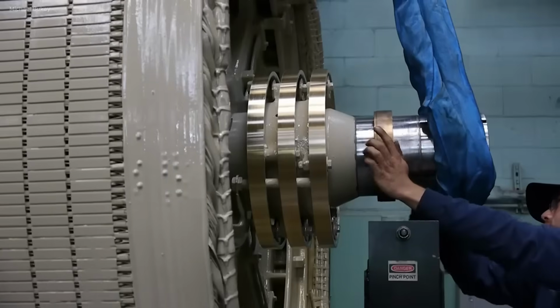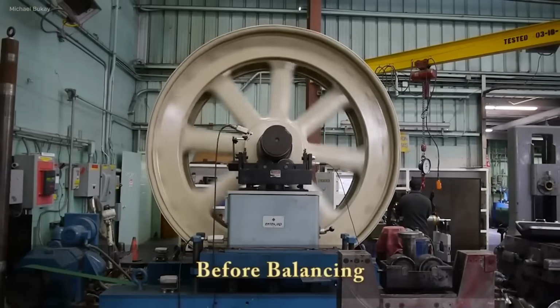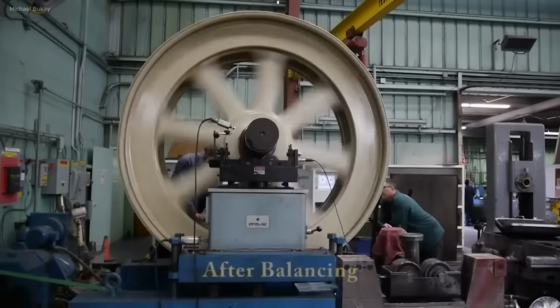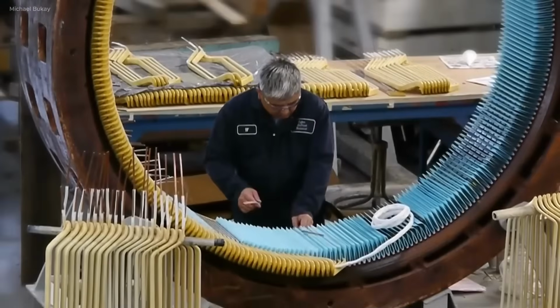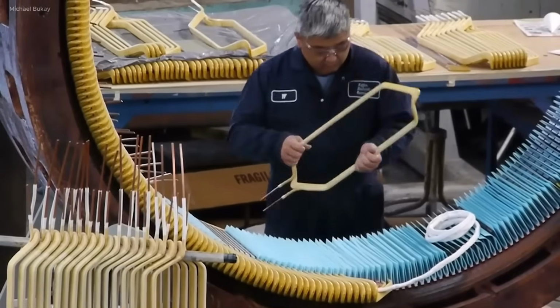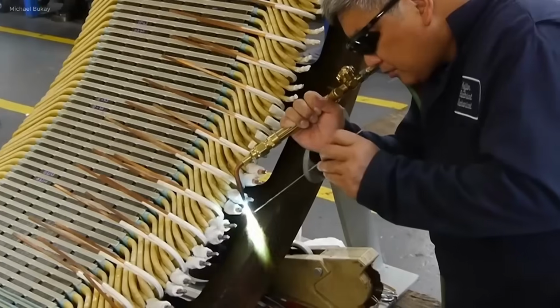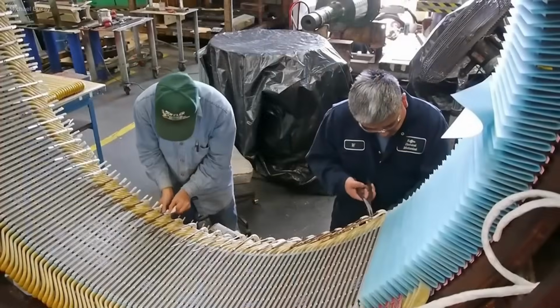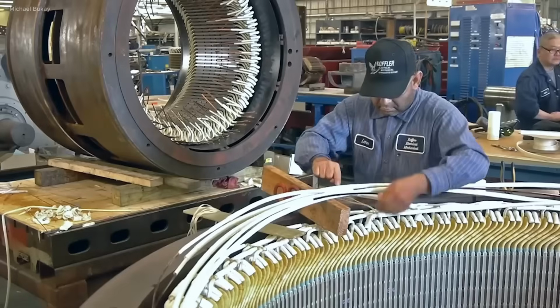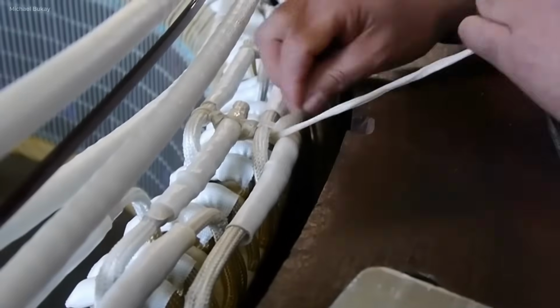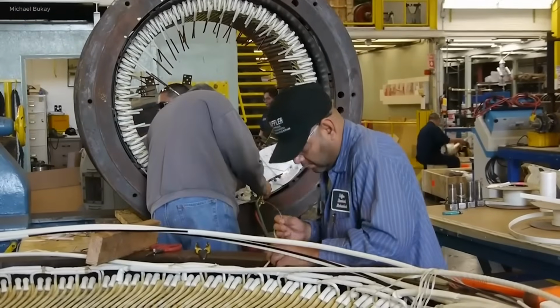After rewinding, the stator is coated with a blue epoxy anti-corona paint to protect against electrical discharge and improve durability. Any excess epoxy is removed to maintain a clean finish. The rotor and other rotating components undergo dynamic balancing to reduce vibration and ensure smooth operation. This step is crucial for motor performance and longevity.